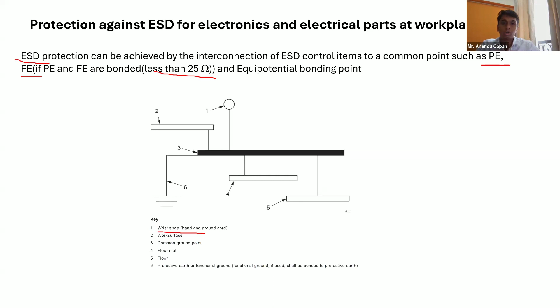Every functional earthing conductor, at the end, has to be connected to the PE, forming a less than 25 ohms requirement. Or you can also connect to a local equipotential bonding point.